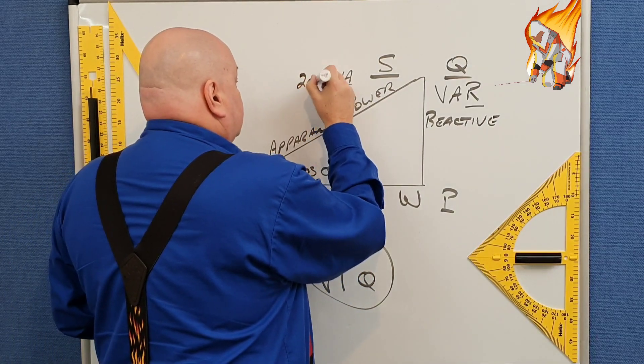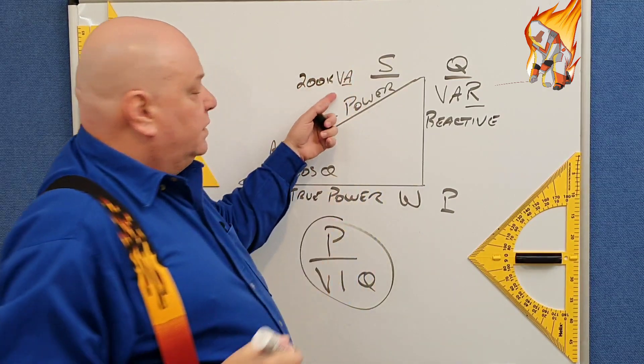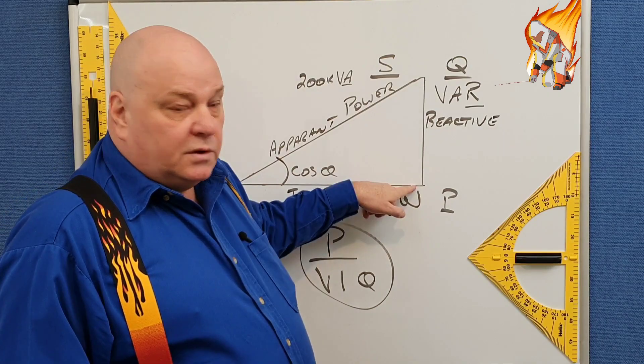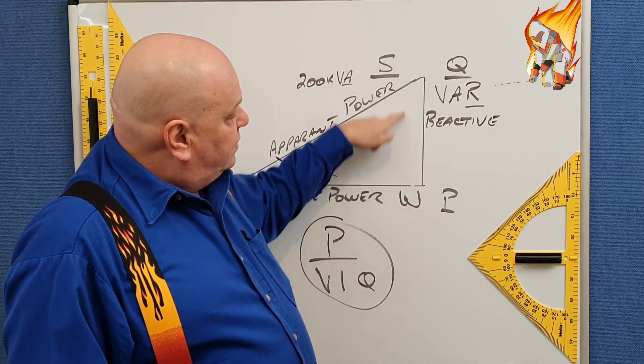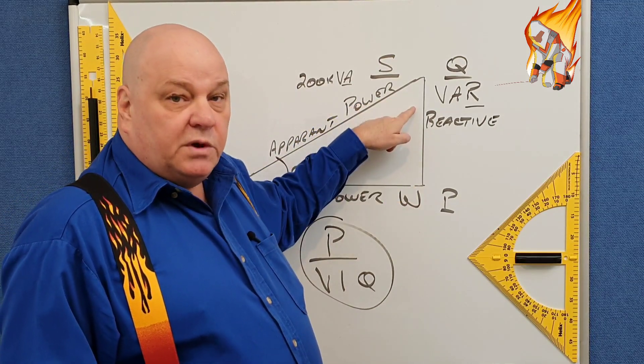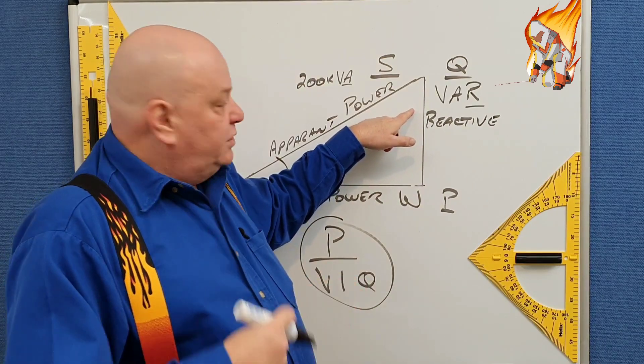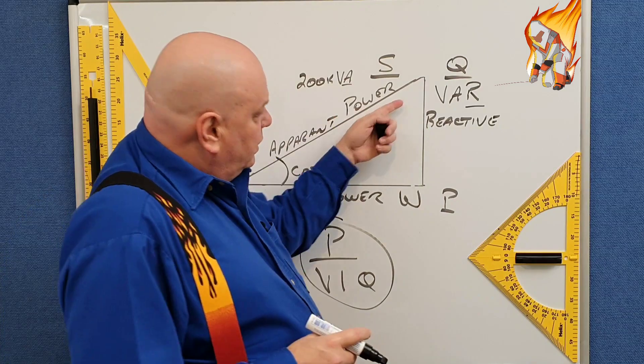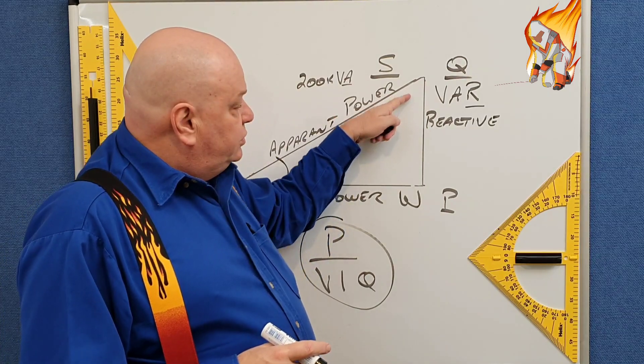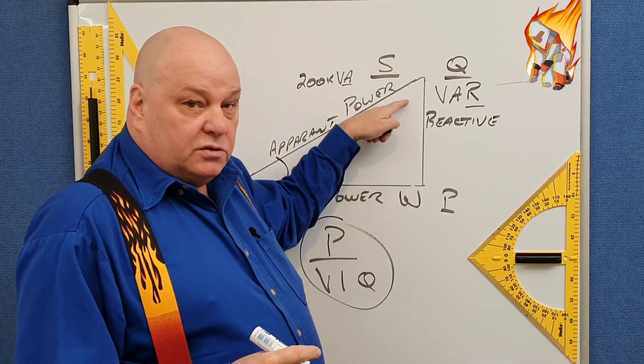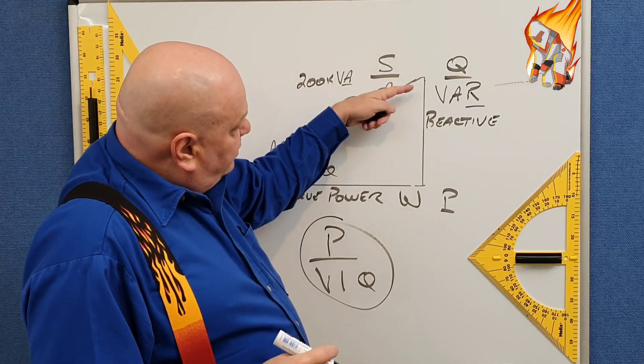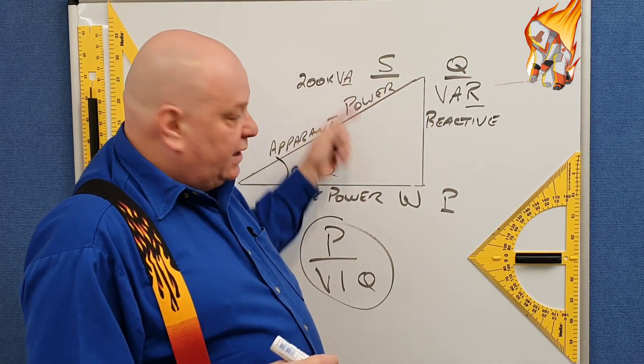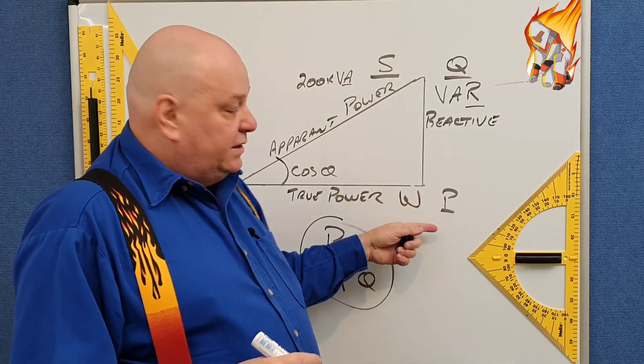So you've got 200 kVA. But it's not giving us 200 kilowatts. It's because of the power that's used up in the reactive component, which is your inductor, which is what's building the magnetic field in the machine. If we were able to reduce the amount of power used in the reactive component, we'd be able to bring that down. And so 200 kVA would provide more power down here.